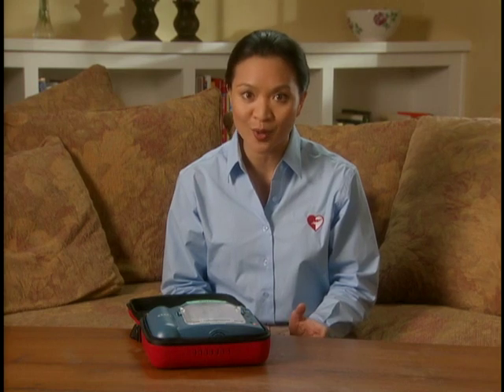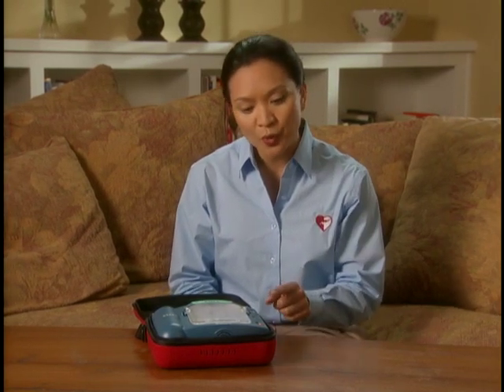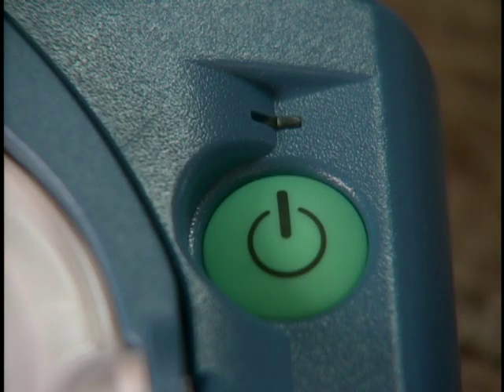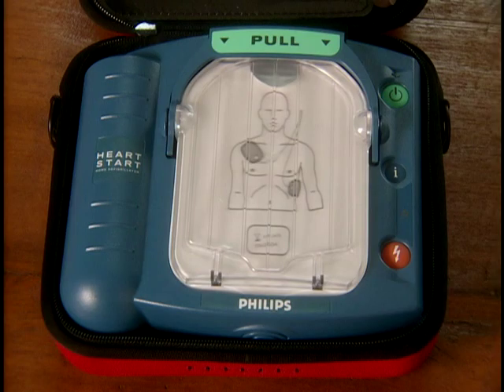The Heart Start home defibrillator is designed to be extremely easy to maintain. As soon as the battery is installed, the device begins a daily schedule of self-tests to ensure its readiness for use. If a problem is detected, or the battery power is running low, or the smart pad's cartridge is not functioning properly, then loud chirping will alert you. Also, the green ready light turns off, and the i button flashes. Press it for more specific information.